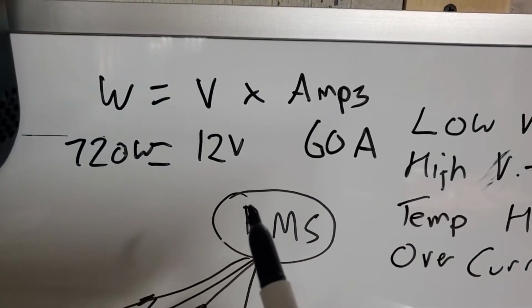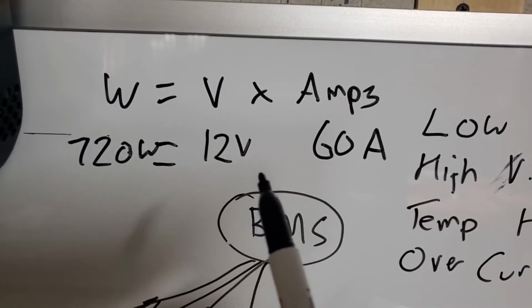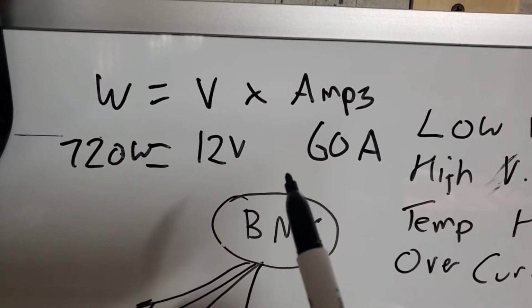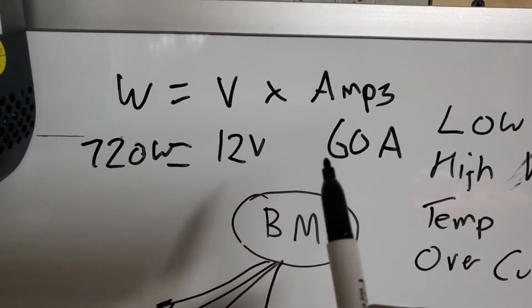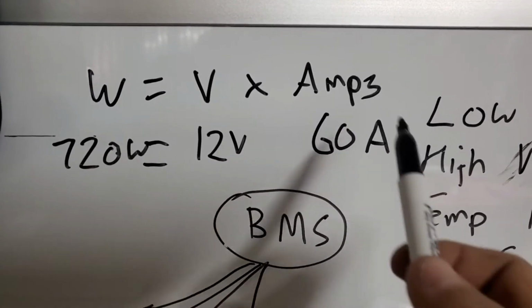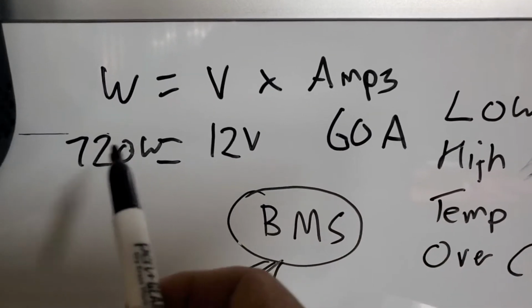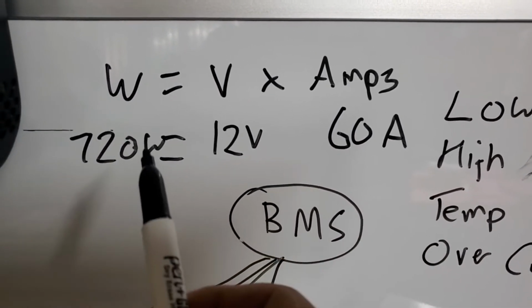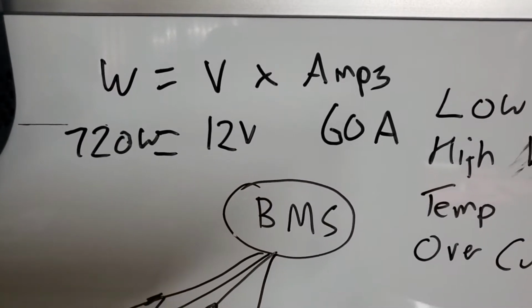All right, you've got this electronic trip switch. So people pull their hair out all the time, going, I've got this massive battery that's 400 amp hours or whatever the case may be, but the BMS is only rated to 60 amps. So that is the biggest amount of surge current that this BMS can handle before it trips.